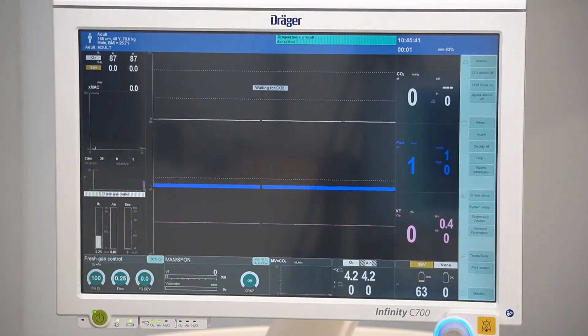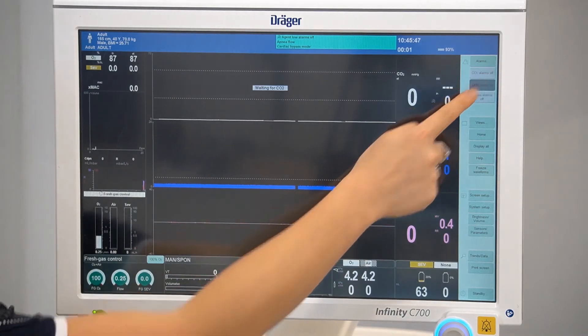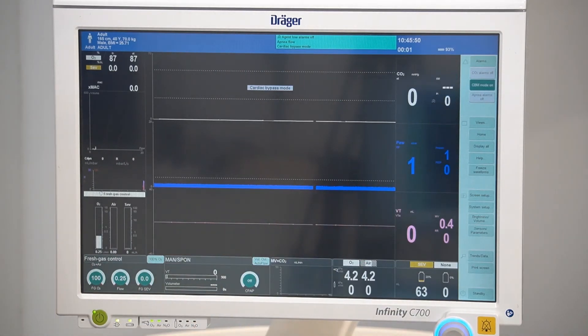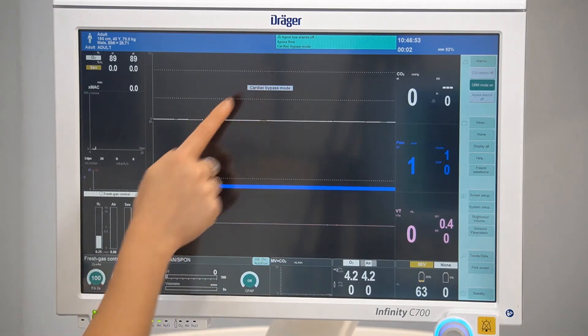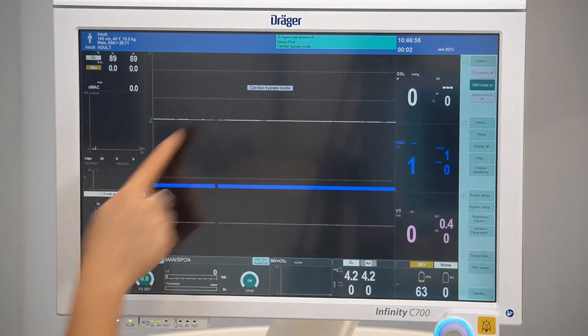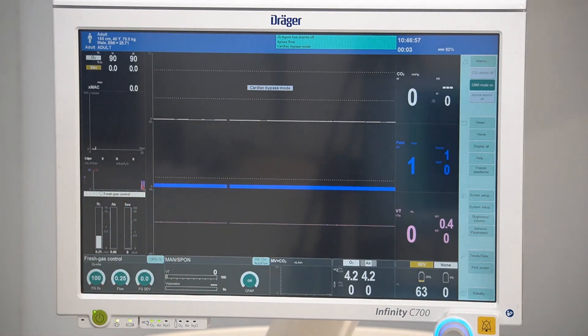To activate cardiac bypass monitoring mode, this can be selected from the right-hand side menu. Touching this button will activate cardiac bypass mode. In this mode, apnea alarms are disabled, and for users with integrated patient monitoring in the Zeus, it will also turn off alarms for ECG, pulse oximetry, and NIBP. A message displayed in the alarm header bar and in the waveform for CO2 will confirm that CBM mode is on.